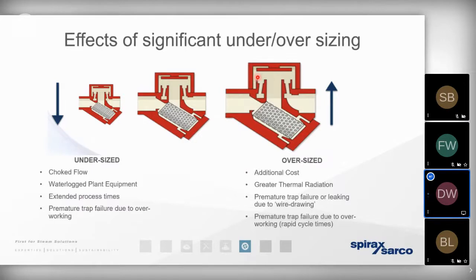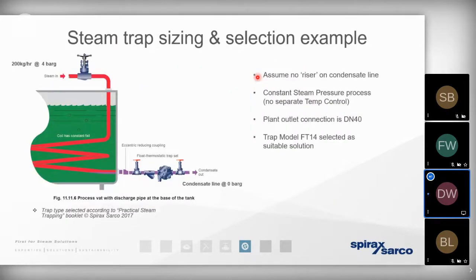So I just want to look at a couple of very quick typical steam trap sizing and selection examples. The first example we're going to look at is a process, and the process is essentially using steam to heat a water tank. So we've got a coil in a tank. You can see that we've got steam pressure at 4 bar gauge. We've got an open-ended line, so we express that as being a 4 bar gauge pressure drop or differential. And you can see that we're condensing 200 kilograms per hour of steam when the process is running. Because it's a process that's required to remove a significant amount of condensate in a short period of time, we're going to use a float trap, or an FT.